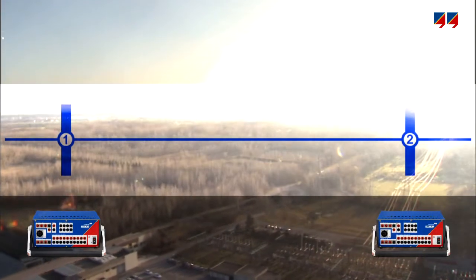Synchronizing two or more CMC units, for instance at the ends of a power line, permits the verification of communication-based distance protection schemes or line differential protection.